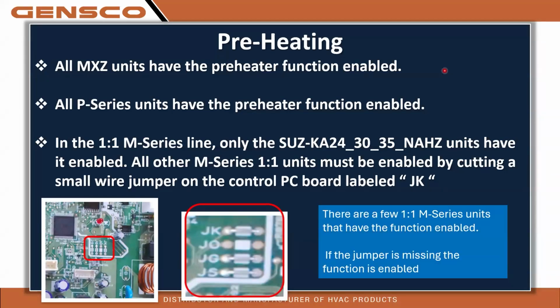If the jumper is not there, and there are a handful of units, the only ones I'm sure don't have this were the GL24, the FH15 and 18. I am not 100% sure of any other unit having the jumper removed and that function enabled, but those three units I am sure of. I don't think it's enabled in the GS24 until I see one to verify that. I can't be sure. So if you're doing an M series unit, MUY, MUZ, SUZ, you must look at this board prior to powering up and find these little jumpers on the board.